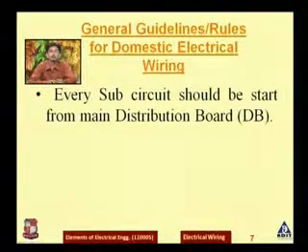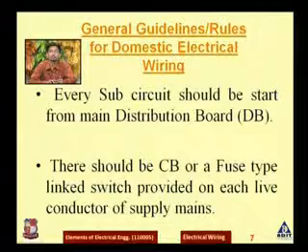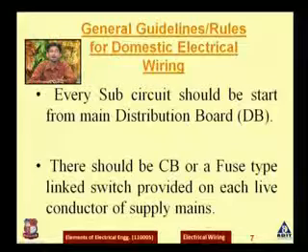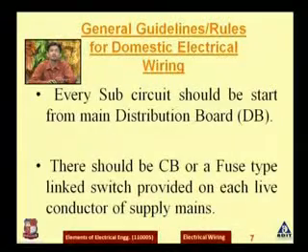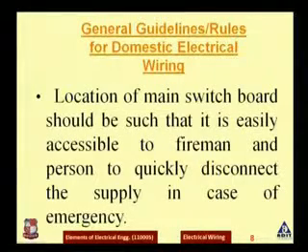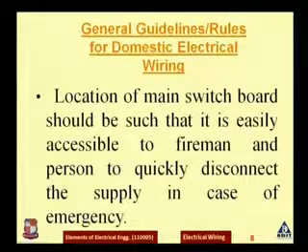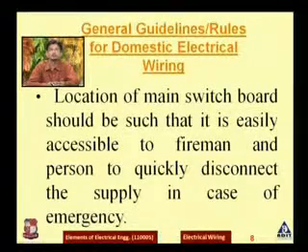Every sub-circuit should start from the main distribution board only. There should be a circuit breaker or fuse-type link switch provided on each live conductor. Nowadays fuses are replaced by Miniature Circuit Breakers, known as MCBs. The location of the main switchboard should be easily accessible to the fireman and to persons who can quickly disconnect the supply in case of emergency or accident.